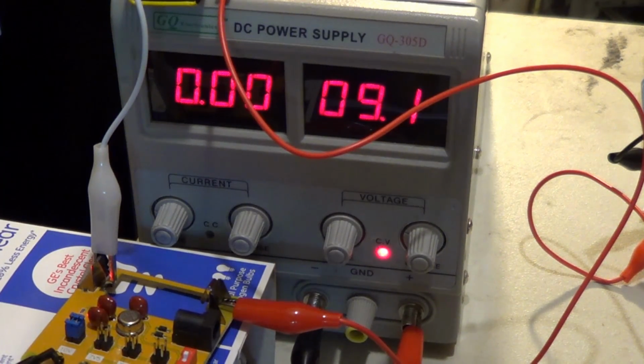What I found is that the test leads seem to be perfectly fine, measuring at least 5 amps worth of current. They don't even get slightly warm in the process. However, the current shunt within the HyperTough meter is definitely the limiting factor, because it got way too hot to comfortably touch after just a minute or two of testing. You should never make a current test that long, especially when the meter tells you the duty cycle is something like 15 seconds on and 10 minutes off.